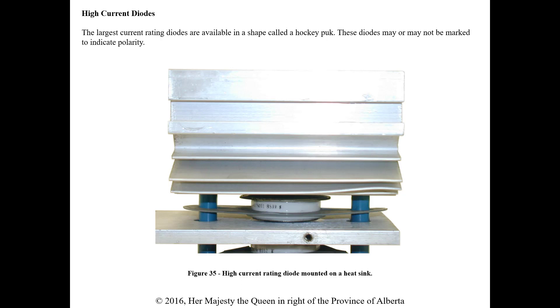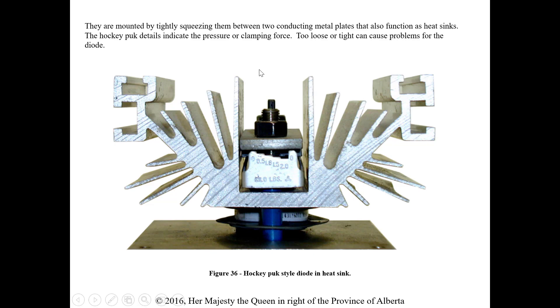High current diodes are available in a shape called hockey puck. These diodes may or may not be marked to indicate polarity. They are mounted by tightly squeezing them between two conducting metal plates, which also function as heat sinks. The hockey puck datasheet indicates the required pressure or clamping force — you may need to use a torque wrench. If it's too loose or too tight it could cause problems. The heat sink shown comes complete with a torque indicator, so a torque wrench may not be necessary — that indicator line shows you what foot-pounds you're at.